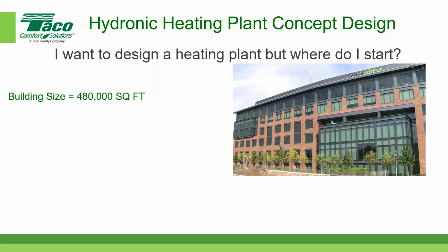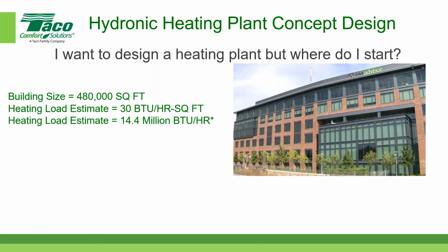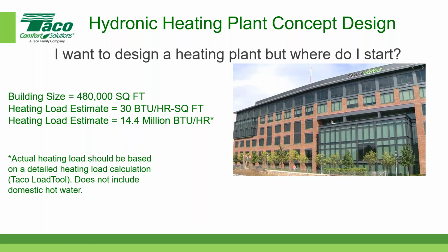So let's keep going. We said the building was 480,000 square feet, and we want to figure out how much the heating load is. One way in New England that we estimate the heating load for a building is to assume that the heating load is approximately 30 BTUs per hour per square foot. And I always tell people that, which you'll see, I have a little asterisk here. If you multiply 30 BTUs per hour per square foot times 480,000 square feet, that comes out to approximately 14.4 million BTUs per hour. And you can see that little asterisk after the BTU per hour. And why do I put that there? Because the actual heating load should be based on a detailed heating load calculation.